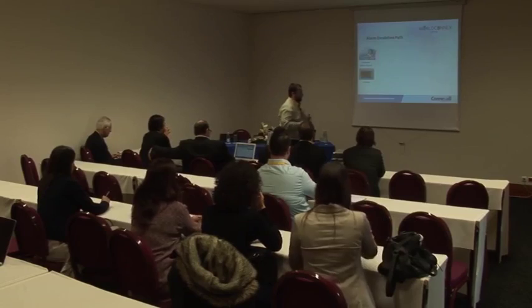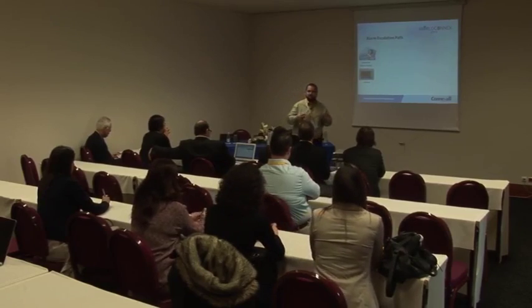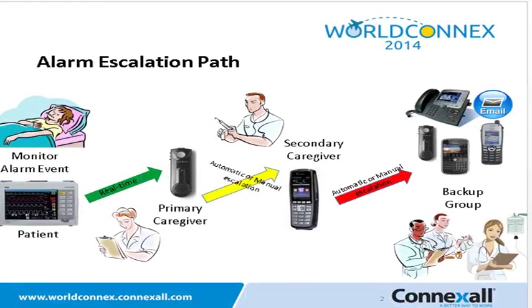We're going to start with the alarm escalation path and how assignments fit into that. When there is an alert or event triggered at the bedside, it immediately goes to what we call the primary caregiver. If the primary caregiver does not have a chance to attend to the patient, is busy on the phone, or is in an area with no coverage, the system should automatically — after a predetermined amount of time — escalate that notification to a secondary caregiver.